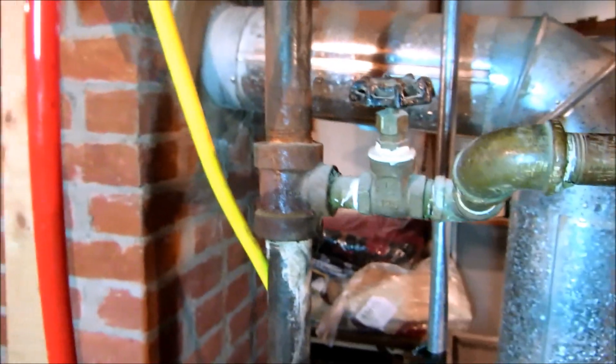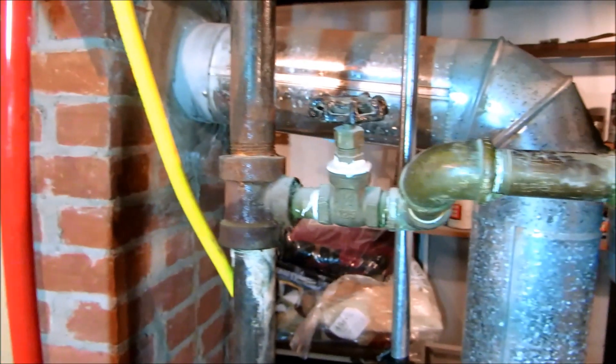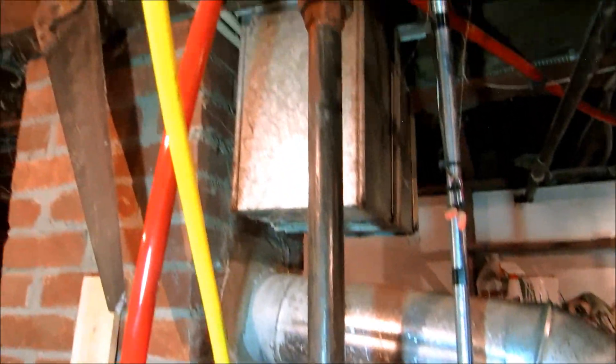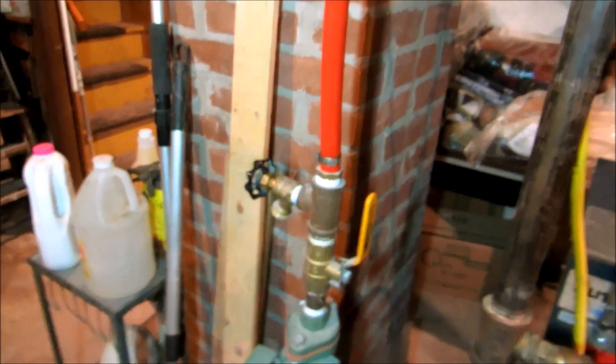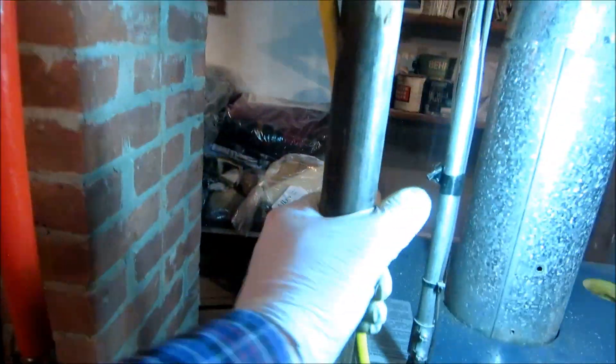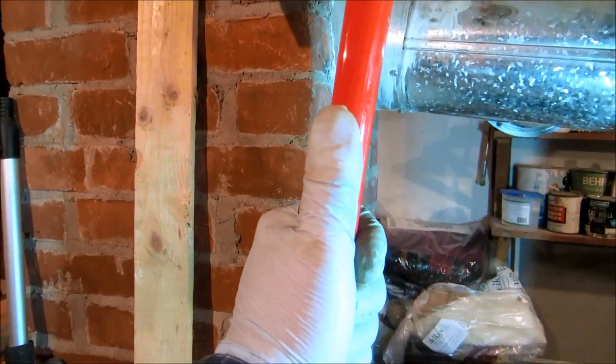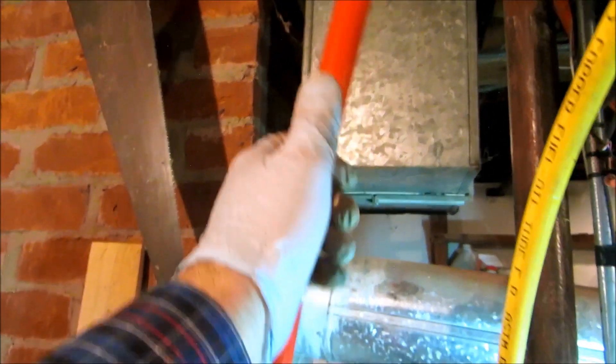So water feeder's going into the return, which it actually should be going into the supply, but I was able to bleed the cast iron radiators upstairs, and this other zone is going to help with the purge out. We're both coming back nice and toasty here, we're both returning, so we're good, it's good to go.